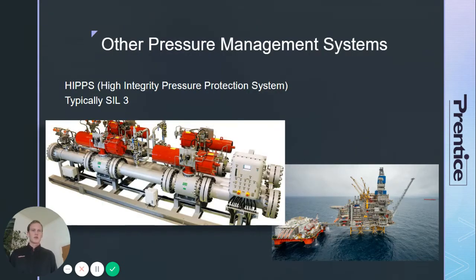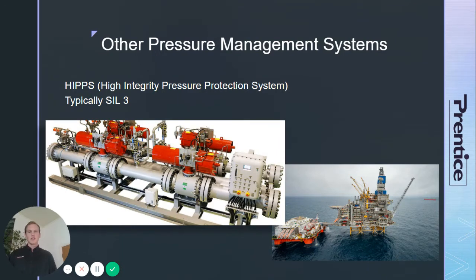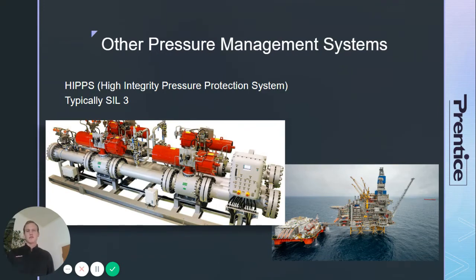On an oil rig or elsewhere in the oil and gas industry, you might see a HIPs system, which instead of using traditional pressure relief equipment, uses automated valves to isolate downstream equipment from an upstream pressure source. On an oil rig, instead of installing a complicated pressure relief system, it's more cost effective to install a small HIPs skid that isolates equipment that can't handle the pressure from the pressure source. These systems have to be redundant because they rely on automation equipment, so they're a little more complicated than a traditional mechanical relief valve.